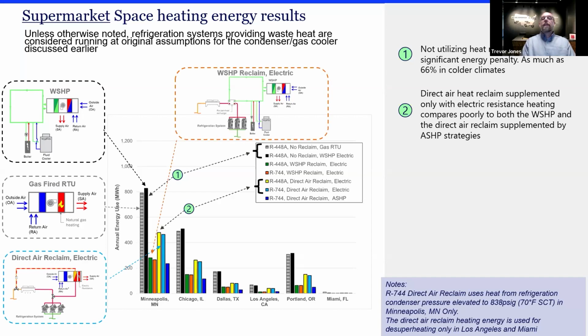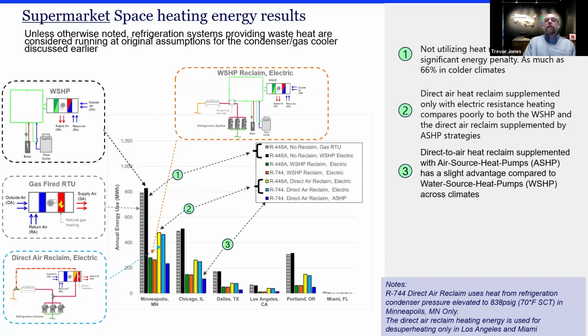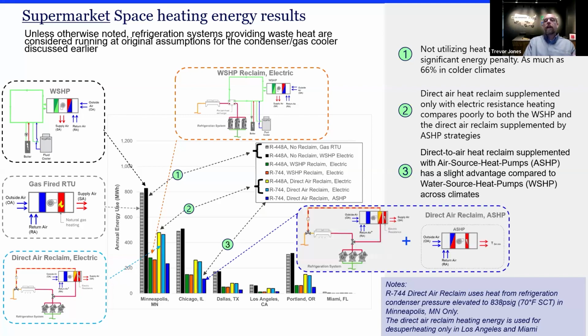So when we started looking at the water source heat pump, because in many climates 20 degrees was kind of the break-even point, the water source heat pump could pull all of the heat out very efficiently, and needed less additional heat. When we started looking at direct reclaim with air source heat pumps, that's when we see a very slight advantage compared to the water source heat pump systems, because we have a larger source with the air source heat pumps to pull heat from the outdoors into the space.